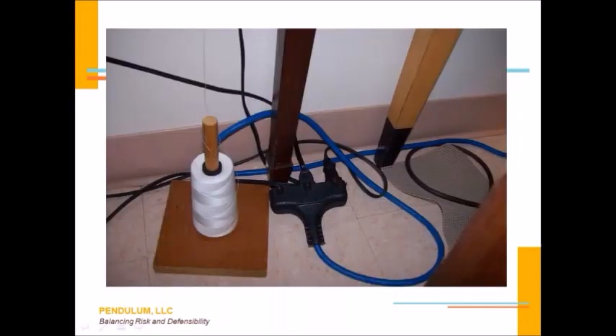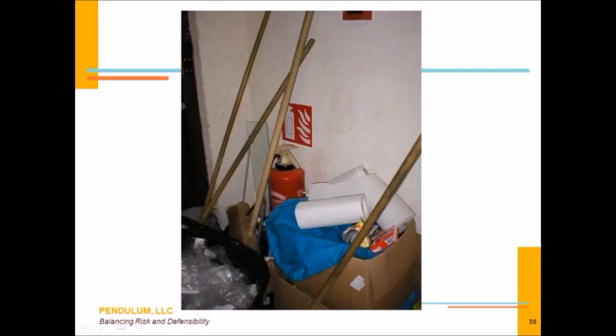And when it comes to the expansion of your electrical delivery system, we all know that extension cords can't be used unless used for a temporary purpose, like for a single, defined action. Like you need the extension cord while you're using a floor buffer. You can use it while you're using it for that specific task, but we can't see them in place like we see them all the time as a replacement for permanent wiring. Do a safety tour of your facility. Go on the hunt for those extension cords and get them out of your facility.